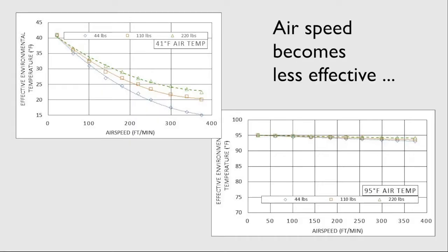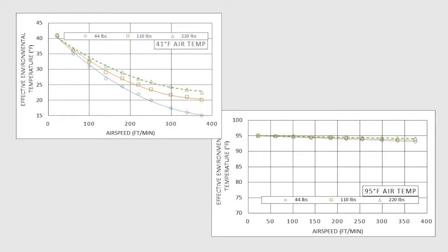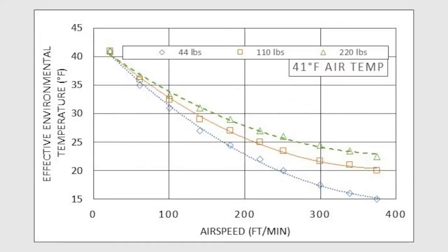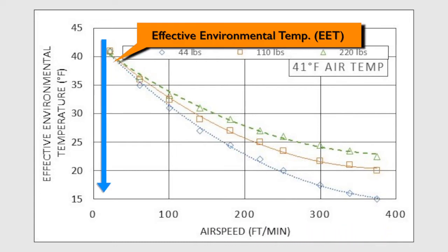Unfortunately, air speed becomes less effective as a cooling method as ambient temperatures get hotter, as these two graphs show. In the first graph, the ambient temperature outside the swine barn is cooler, 41 degrees Fahrenheit. As the air speed increases from 100 to 200 to 300 feet per minute and higher, there is a dramatic decrease in the effective environmental temperature, or EET.